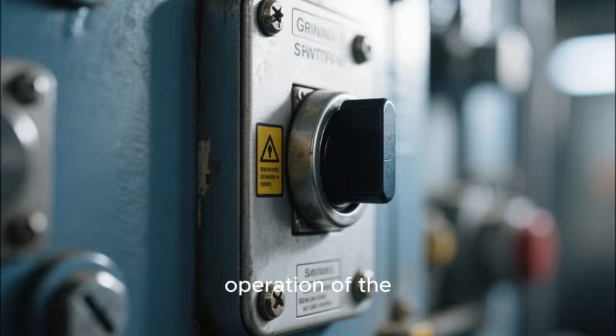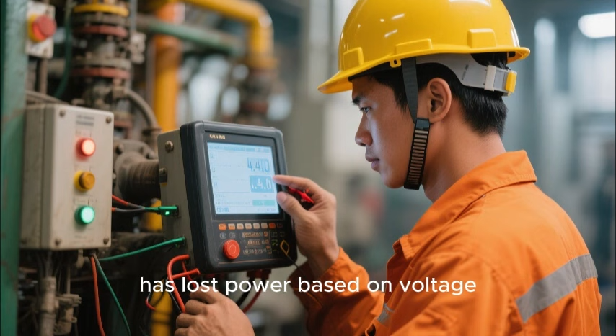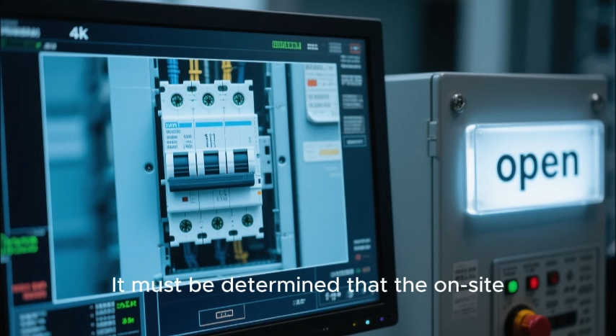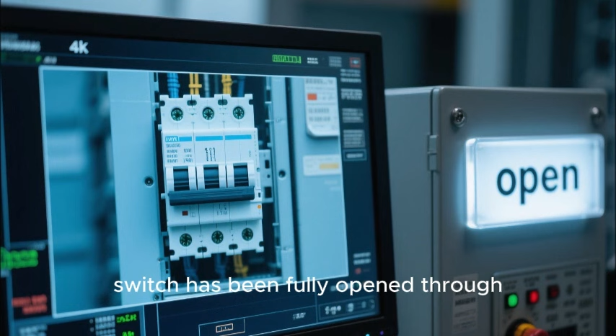Under what conditions is remote operation of the grounding switch allowed? Answer: the interlock circuit of the grounding switch has been tested, accepted, and put into operation. It must be determined that the line or electrical equipment has lost power based on voltage parameters or confirmation from the operator present at the power station. It must be determined that the on-site status of the circuit breaker and related isolating switch has been fully opened through confirmation from the operator at the location of the switching device or the operation monitoring camera.